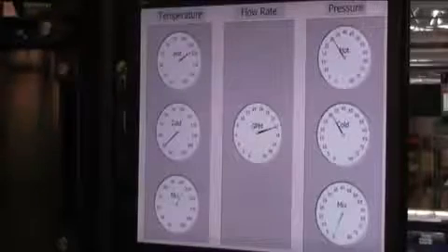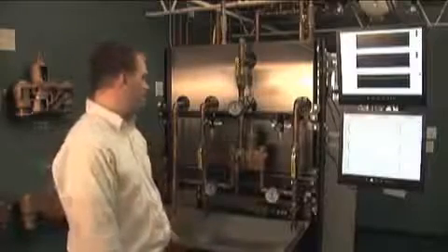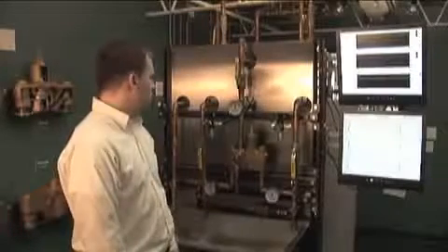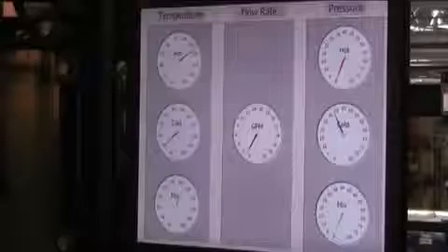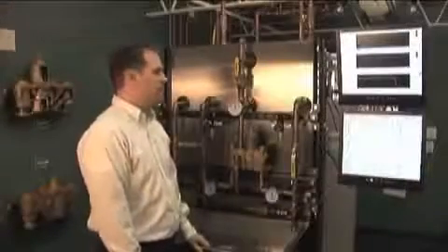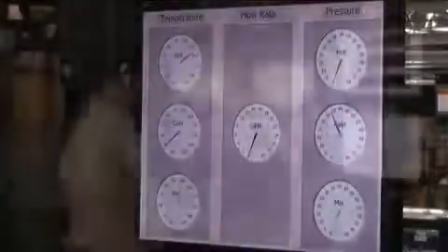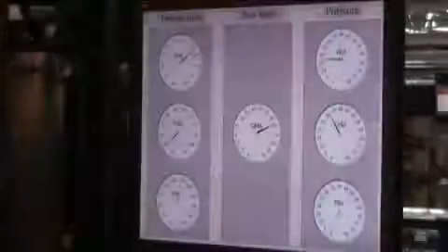Now what about the catastrophic events that might occur? What happens if the valve were to lose hot or cold water at any time? If the valve loses the hot water, the thermostat responds by shutting off the flow from the mixing valve. Almost down to nothing, within a half a gallon or less. Once I reintroduce the hot water into the valve, within a matter of seconds, I will come back to the desired set point.